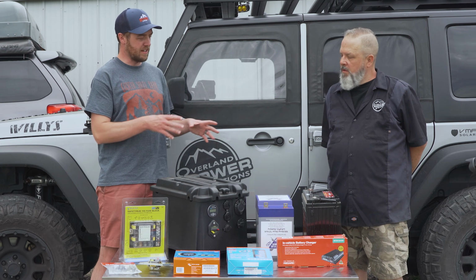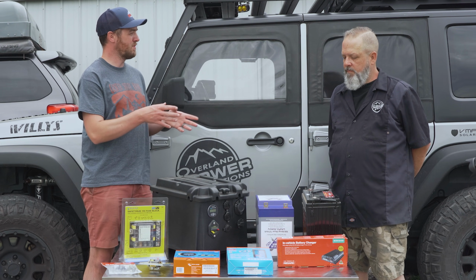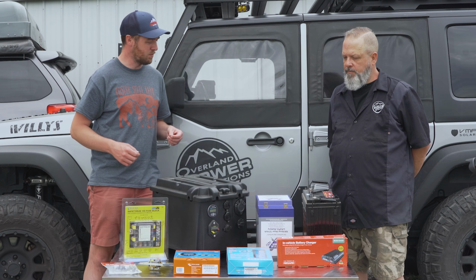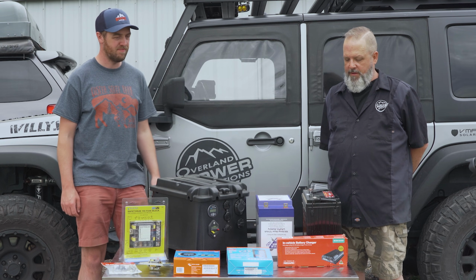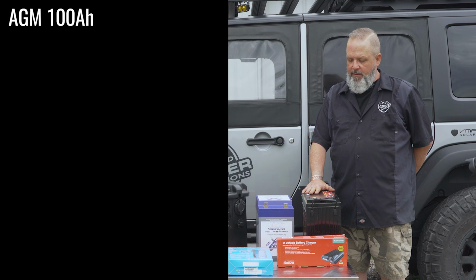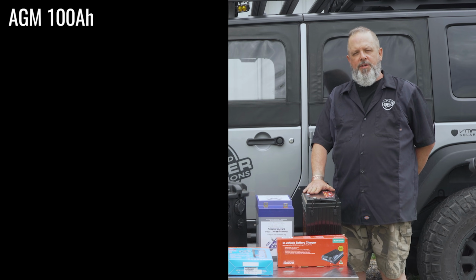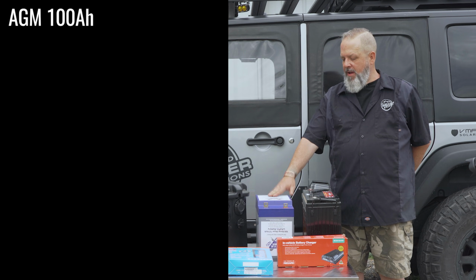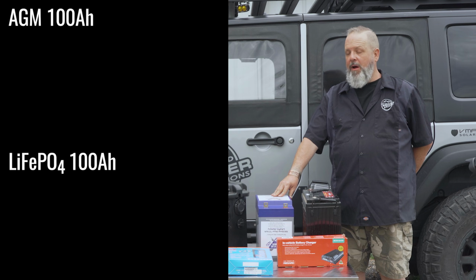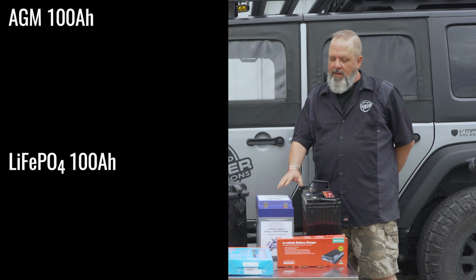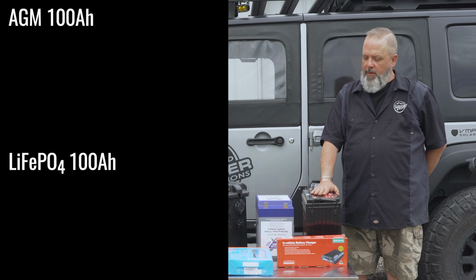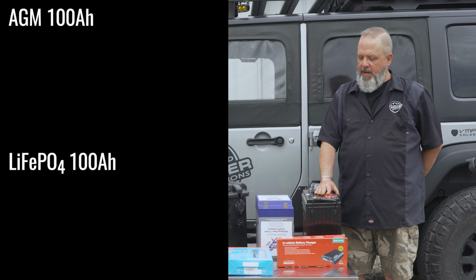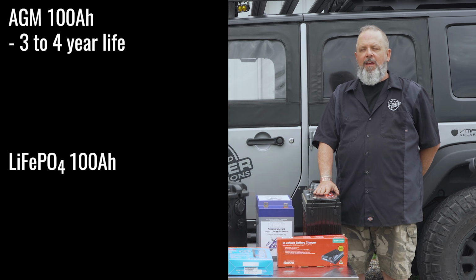Let's go over some of the differences between these two. Tell us about capacity-wise, advantages of one versus the other. So the AGM sitting right here is a 100 amp hour AGM battery. The battery next to it is a 100 amp hour lithium ferro-phosphate battery. The battery on the left has a typical lifespan of about 3 to 4 years, if and only if you're actually charging it with a smart charger that understands the battery chemistry correctly.